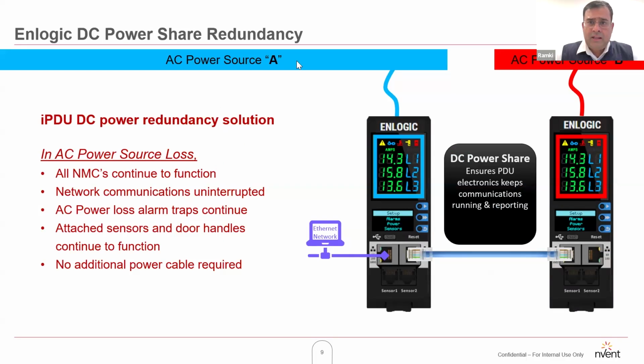Another use of the dual Ethernet ports on the PDU is in a typical data center setup with source A and source B power for each rack. With two PDUs installed and the redundant Ethernet port interconnecting them, if you lose source A or source B, you can still communicate to the NMC of that failed source PDU. So even though you've lost power on that PDU, you can still reach its network management controller through the redundant Ethernet port.